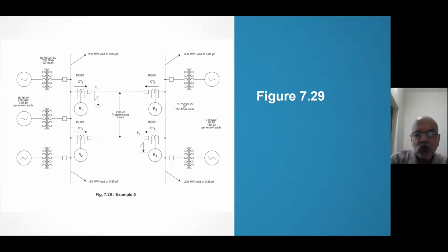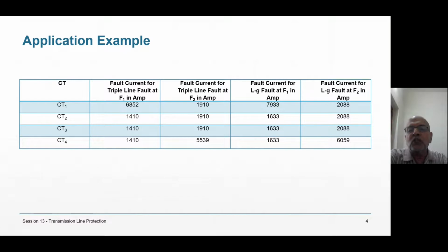F1, F2 fault currents are given, earth faults. Now the earth faults I will have to give. System is the same, 1500 by 1 ratio on one side, 1000 by 1 ratio on the other side. One side 3 generators, the other side 2 generators. 15.75 by 220 kV, 210 megawatt, 0.85 PF. Loads are given. Everything same. But the load currents will differ. Fault currents for loads I have used for LG faults, that you have to remember. Last time we used for LL faults.